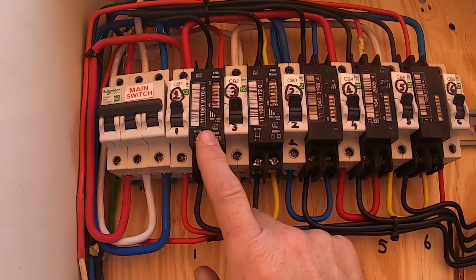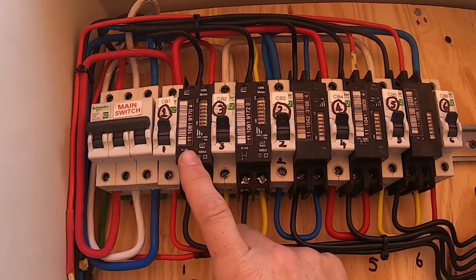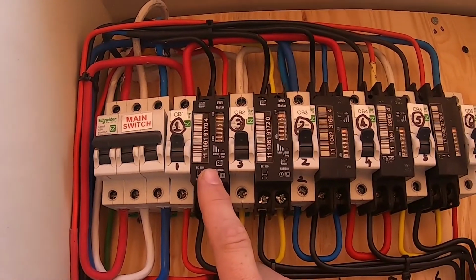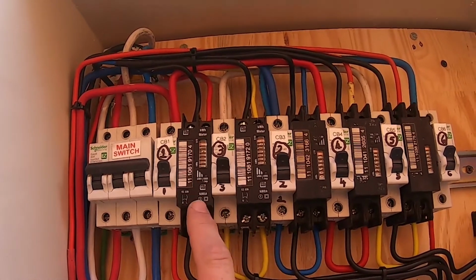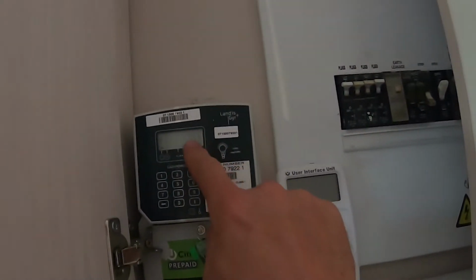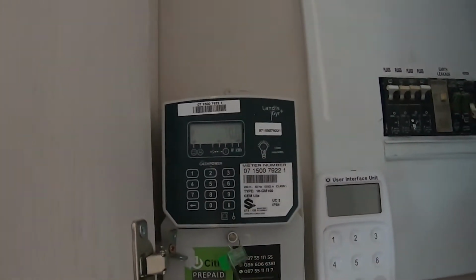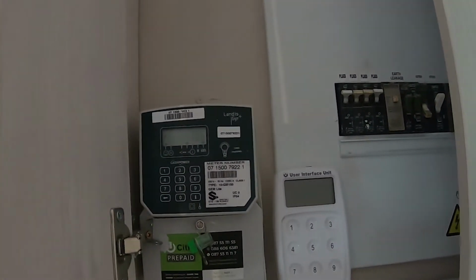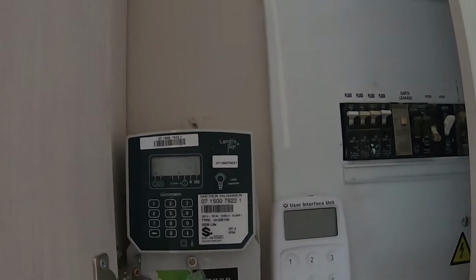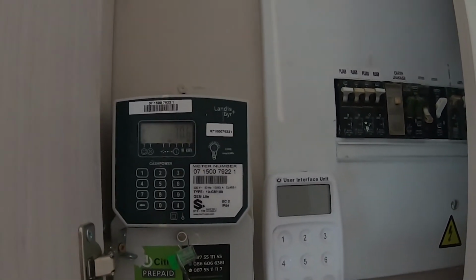In that way, I can see if at any stage a tenant has bypassed electricity, in other words, tried to bypass their prepaid meter, because I can actually see how many units of electricity they use here, and I can check that, for example, against the number of units that the tenant is buying and using here. In that way, I can make sure that it is fair and the tenant is using the correct amount of electricity that they are buying.